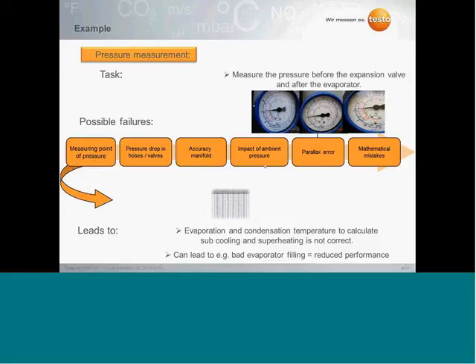And the impact of ambient pressure. Depending on the ambient pressure, whether we are at sea level or in the mountains, our values can also change. Then on analog manifolds we have a high risk of parallax error. You can see this very well in the pictures above. Depending on the angle you look at the gauge, you will see different measured values, which is also a risk of failure. And of course, we can make mathematical mistakes. We can, for example, check the pressure of the system and not correctly calculate the condensation or evaporation temperature of a refrigerant. These failures can occur, and this of course leads to wrong evaporation and condensation temperatures, which are the basis for calculating subcooling and superheating.